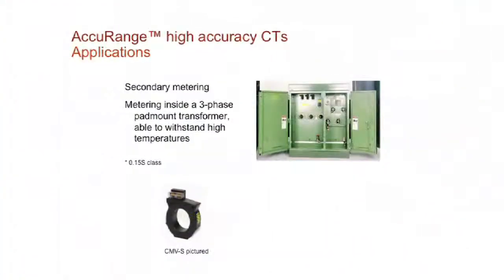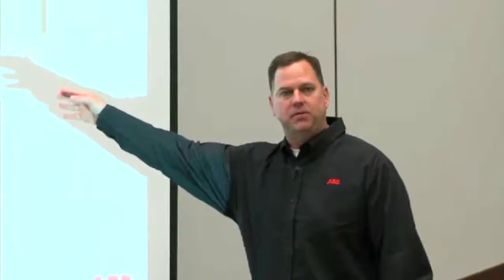We also have one that's very commonly found in pad-mounted distribution transformers. Okay, this is called the CMVS. Okay, you would see these outside of slightly larger installations, a green box and typically a meter on this side of that. And so, we have ones that are specifically designed just for that. One of the other nice things about these here is that they are able to withstand higher heat because what will happen, especially in the summertime, especially in the south or in high temperature climates, the temperature inside there will become very hot. CTs typically will derate for accuracy once the temperature becomes very high. These are specially designed to withstand temperatures up to 85 degrees C inside that pad-mounted distribution transformer.